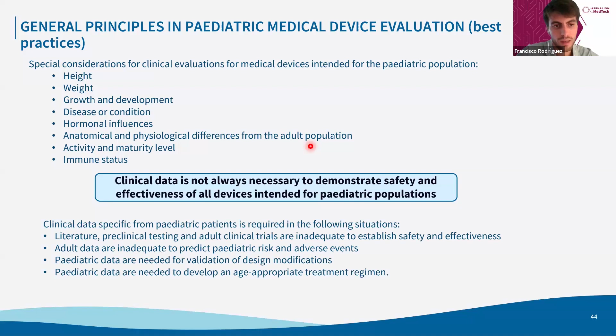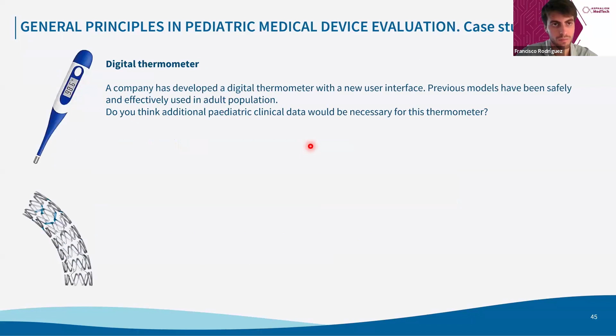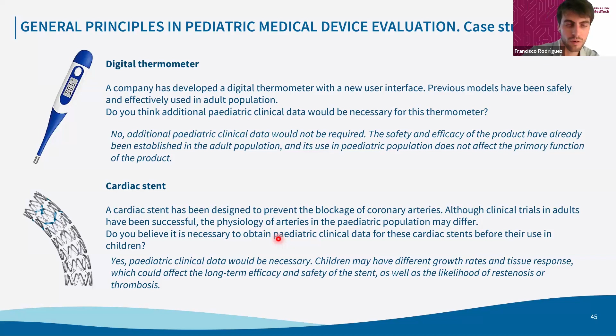Okay, these are key differences between the pediatric population and the adult population that in some cases will prevent us from using as evidence clinical studies that are already there for adult populations. Okay. So for these cases, you will need to conduct specific clinical trials with pediatric patients. Here you have some examples, okay, of when you can demonstrate that the clinical evidence that you already have is enough to support the use of your device in a pediatric population, okay? So for example, whenever you can define that there is no impact on the safety or the performance of your device between an adult or a pediatric population, you can still rely on your data coming from an adult population to use your device also in a pediatric population. So I will leave this here for your consultation.